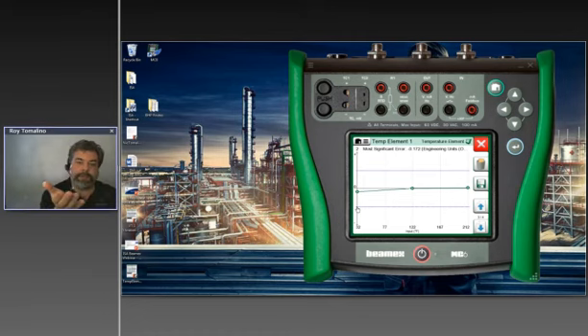That temperature is coming in, well, in this case, from the bottom underneath the insert, but there's usually a delay. You need to leave time so your temperature element can acclimate and come to the same temperature. So I needed to add in a 3 to 5 minute delay after the dry block achieved my temperature and before I actually accepted the test points. If I wanted this to be a fully automatic calibration, I probably would have put in a 5-minute delay between each test point, which would give me a very accurate line, which is what I'm seeing right here.